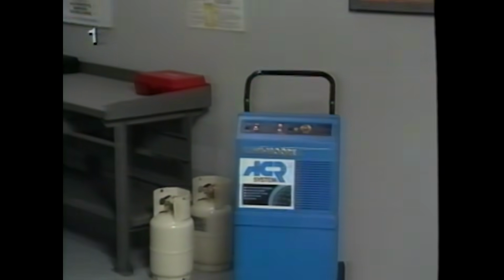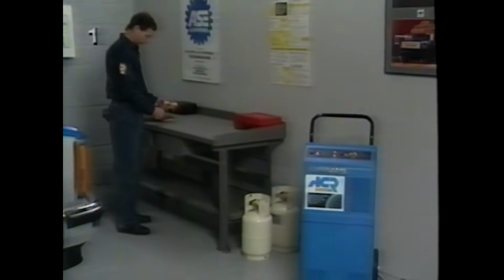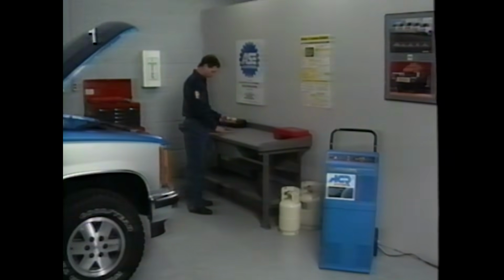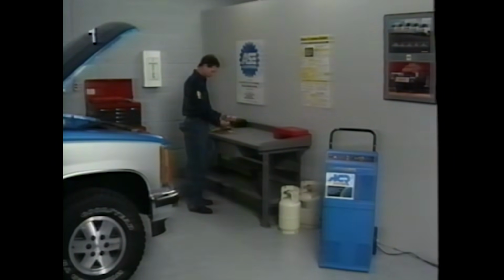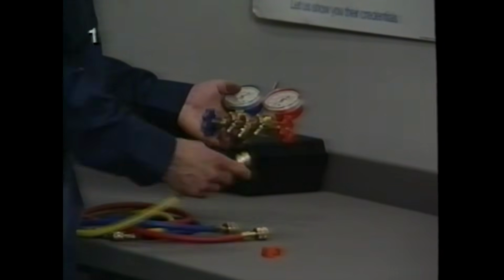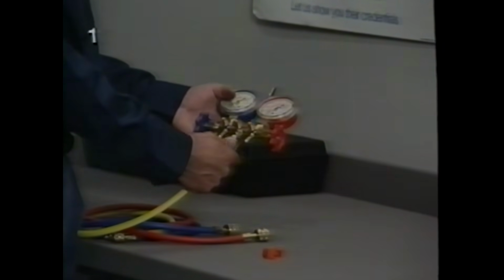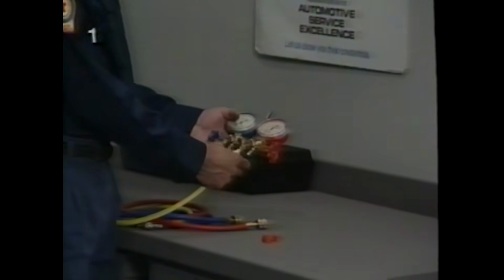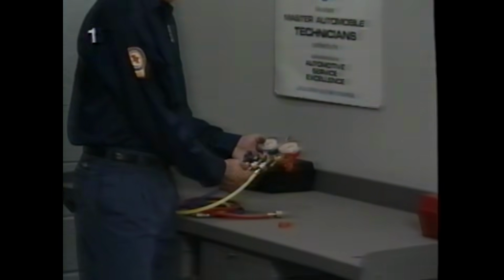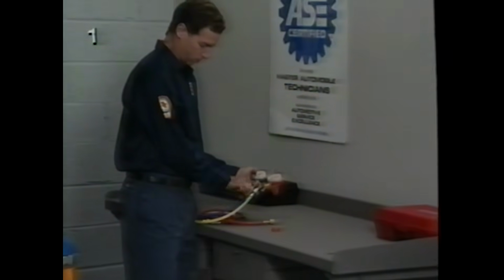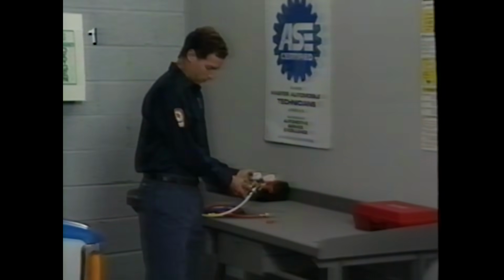The air conditioning reclaiming and recycling station makes it so you don't have to vent refrigerant 12 to the atmosphere, and it works with your existing shop equipment, manifold gauges, and charging stations. Three new hoses that come with the ACR3 go on the manifold set and charging station. These hoses are designed to keep Freon from escaping to the outside air.